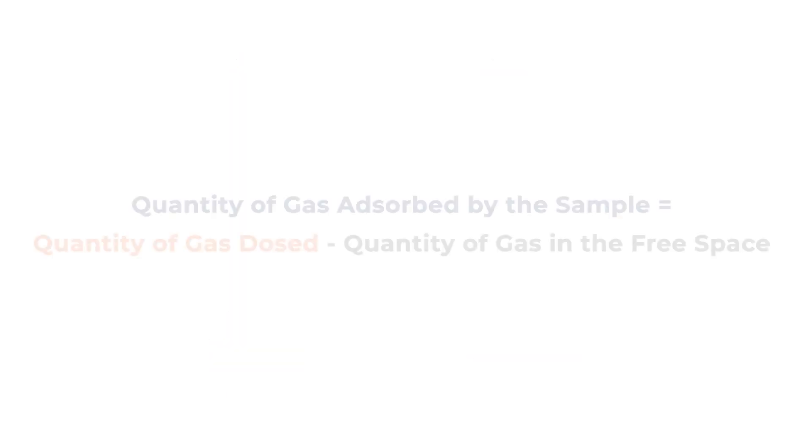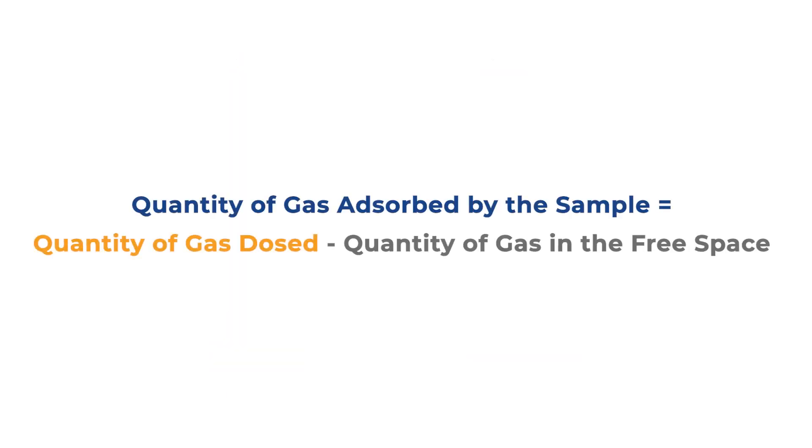It is important to know this value so when a known volume of gas is dosed, the volume of gas occupying the void space above the sample can be subtracted to accurately calculate the quantity adsorbed by the sample.